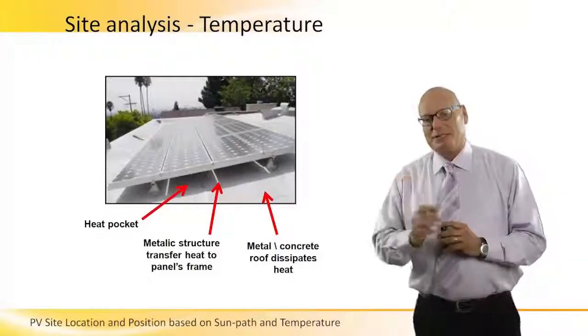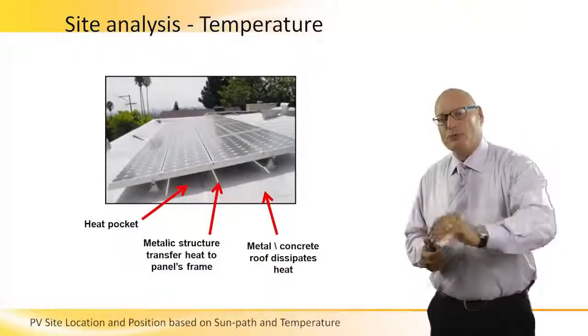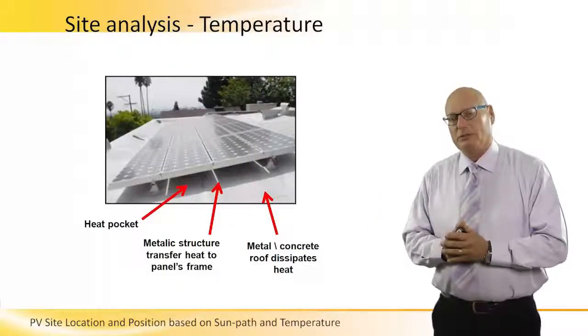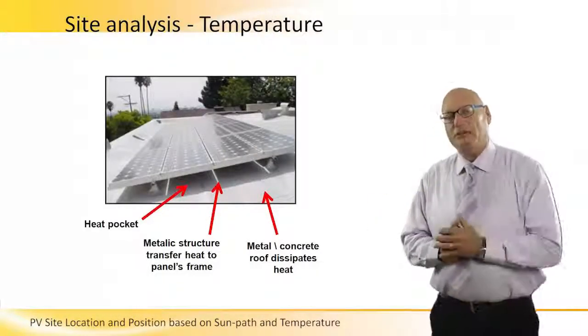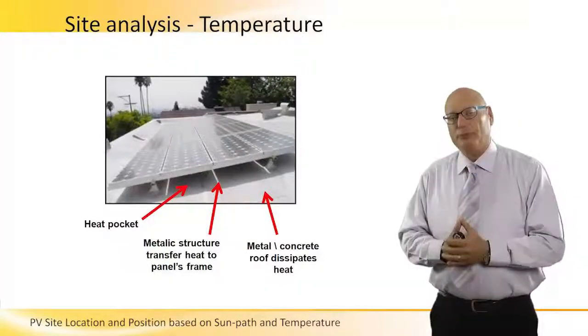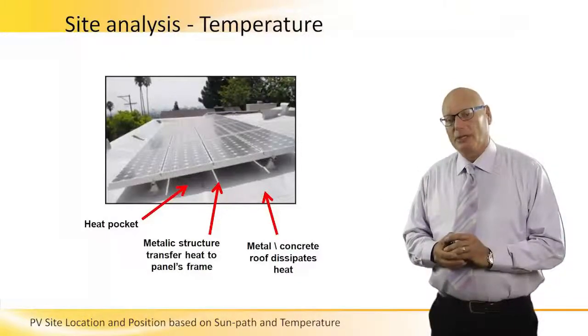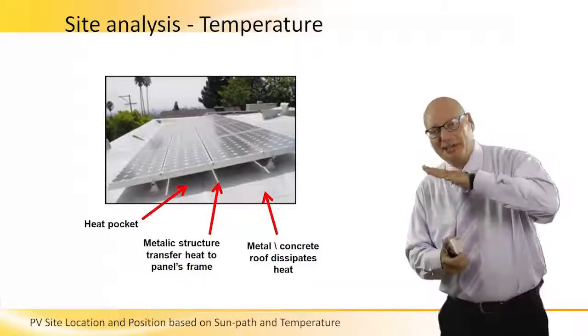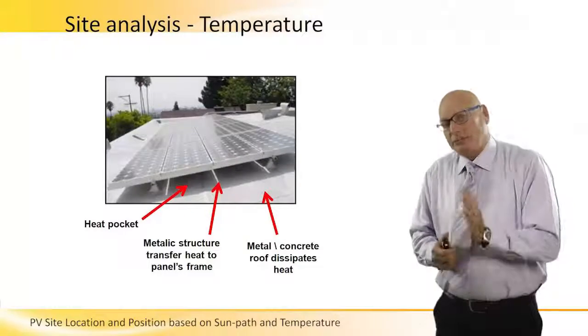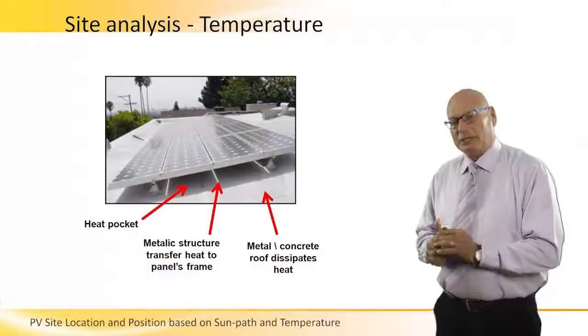When we do a site analysis, as we discussed before, we consider the type of roof on which we want to place our array. If the roof is metallic and getting hot, heat waves coming up reflected away from the roof will heat up the panels, creating a heat pocket between the layer of panels and the metallic layer of the roof itself. That's number one — this heat pocket.